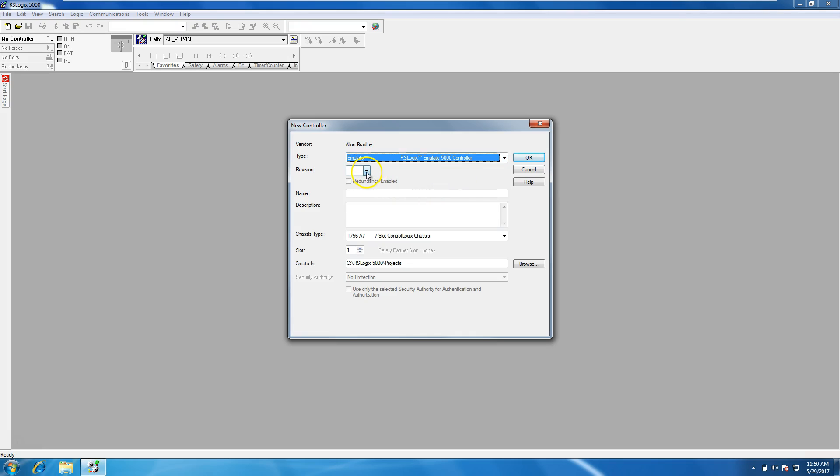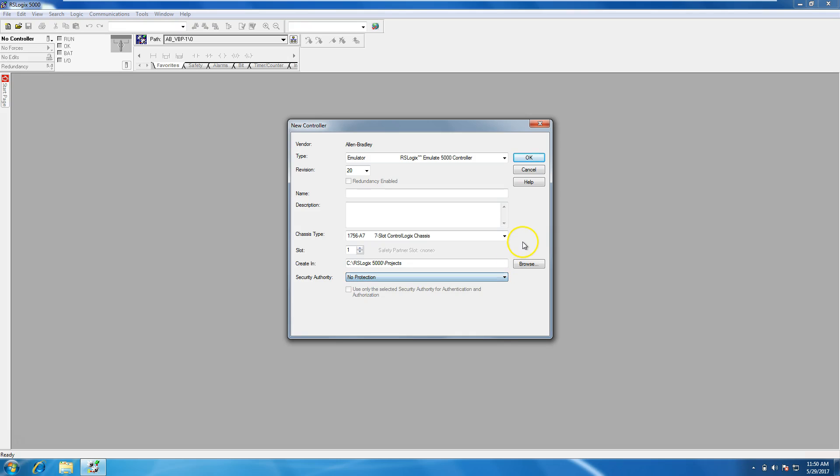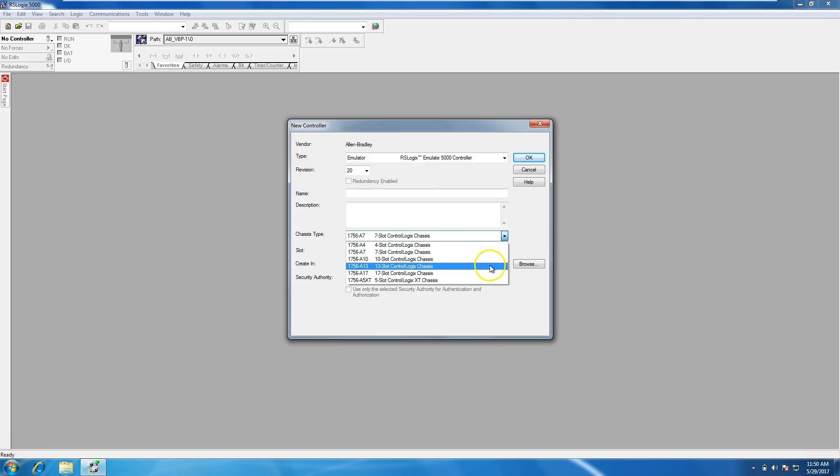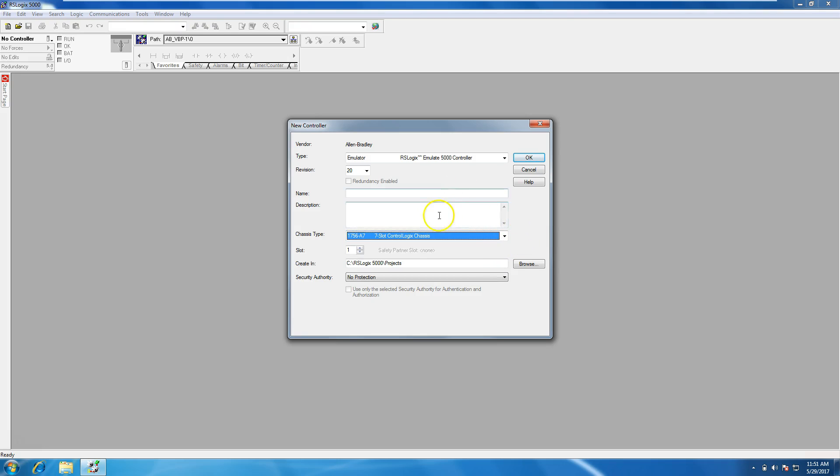We're going to select our version. Our version is going to be version 20. And you can select your slot type, which we want to be in slot either 0 or 1, which in this case 1 is fine. You can do your security authorization if you want to have security authorization just to a specific group or computer or something of that nature. You can select your chassis size, whether you're using a 4 slot, 7 slot, 10 slot, 13, 17, or of course down here the more robust system.